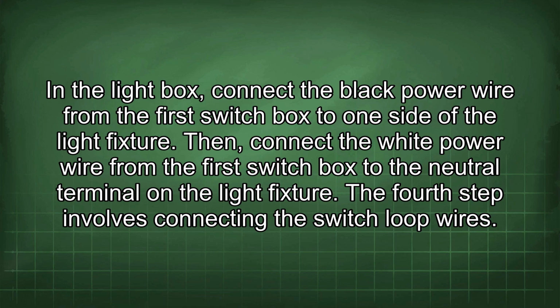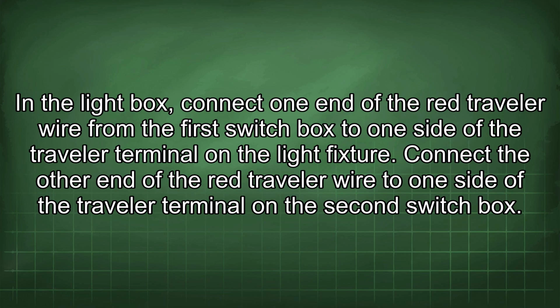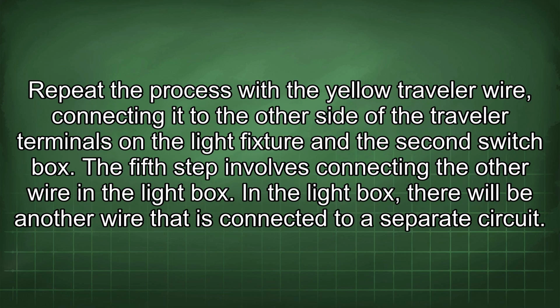The fourth step involves connecting the switch loop wires. In the light box, connect one end of the red traveler wire from the first switch box to one side of the traveler terminal on the light fixture. Connect the other end of the red traveler wire to one side of the traveler terminal on the second switch box. Repeat the process with the yellow traveler wire, connecting it to the other side of the traveler terminals on the light fixture and the second switch box.